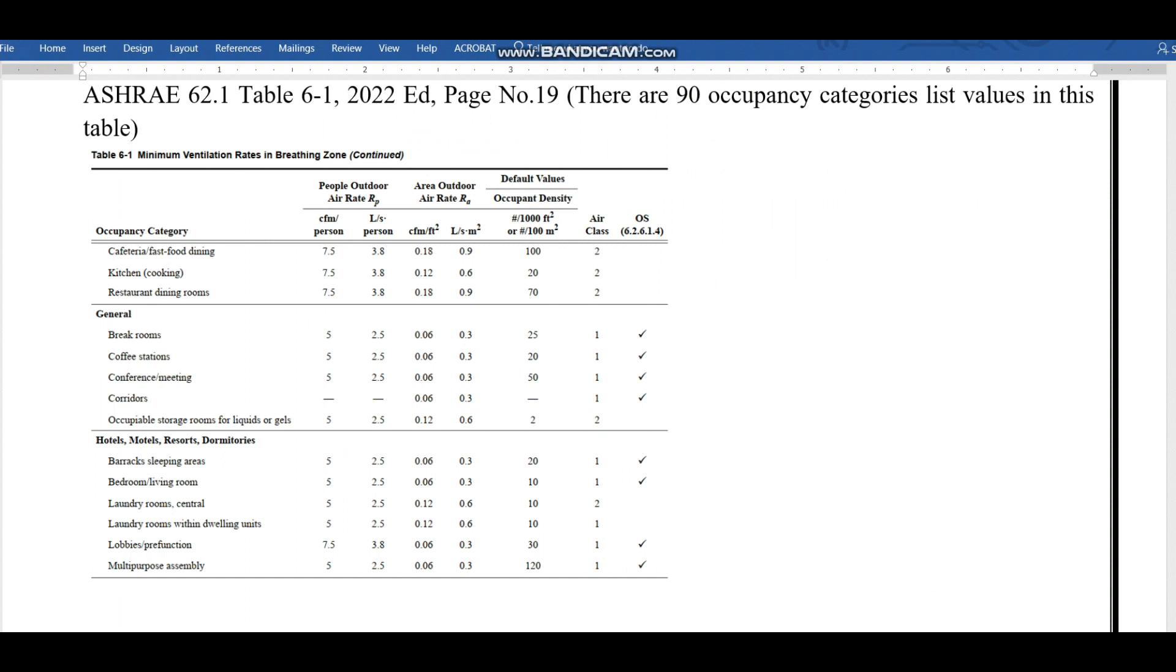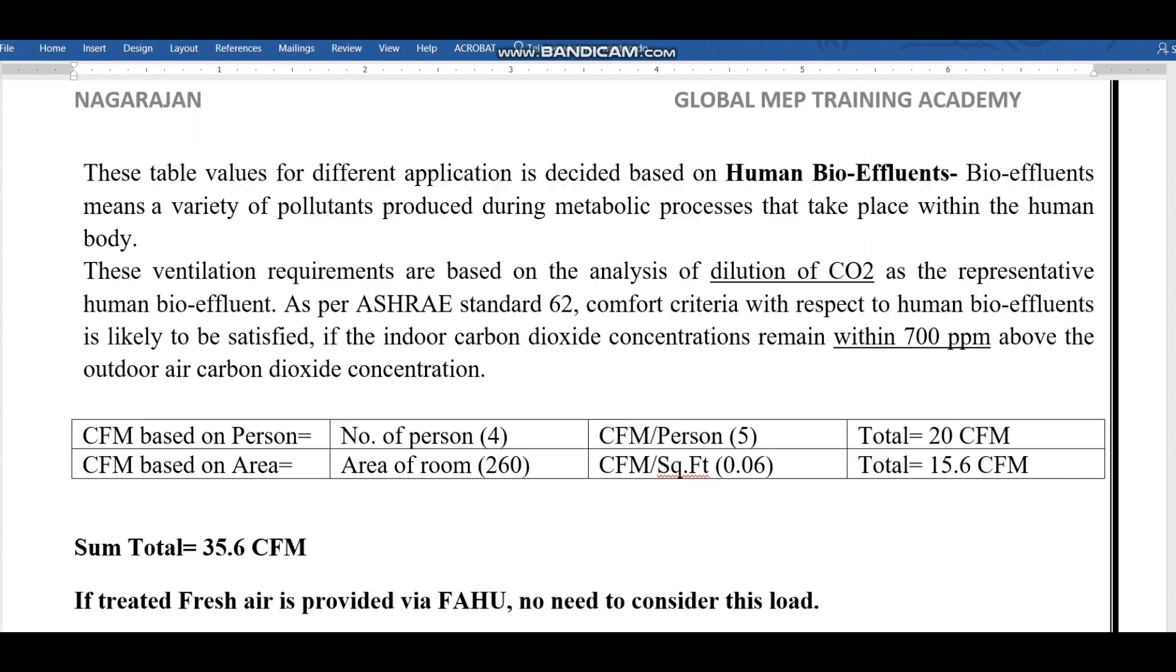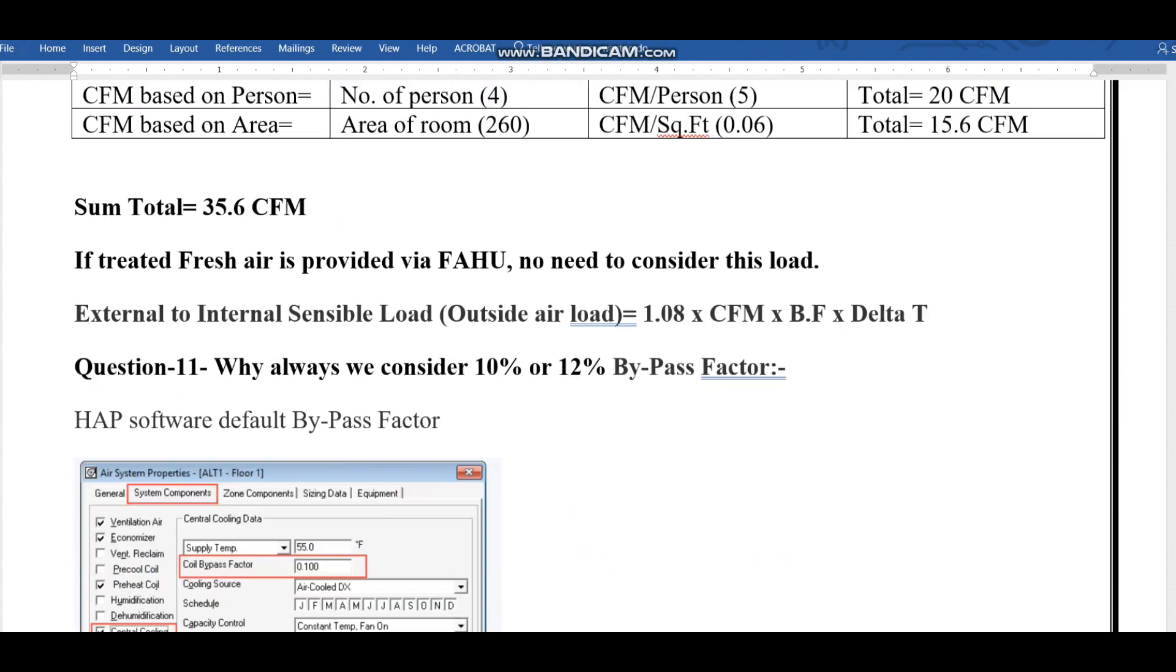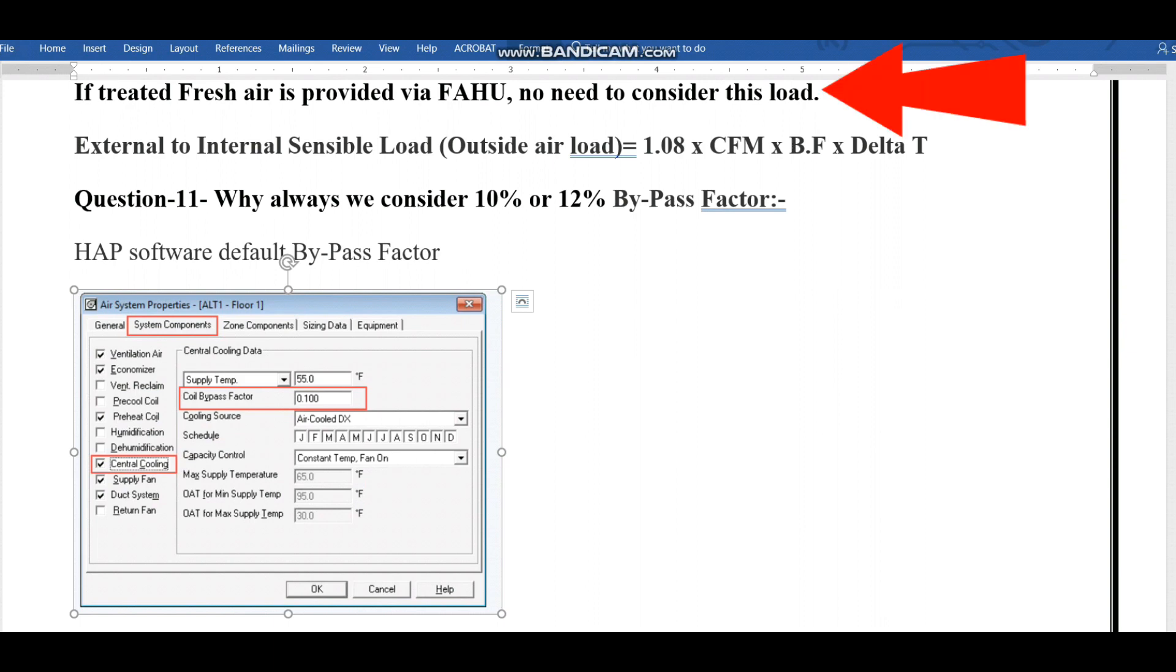For example, for hotel bedroom or living room we need to consider 5 CFM for one person and 0.06 CFM for one square foot. I applied the numbers: number of persons 4 times 5 CFM per person is 20 CFM. The area of the room is 20 times 13, 260 square feet, times 0.06 CFM per square foot equals 15.6. Total is 20 plus 15.6, which is 35.6 CFM.